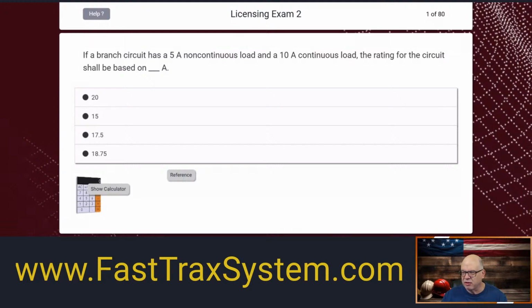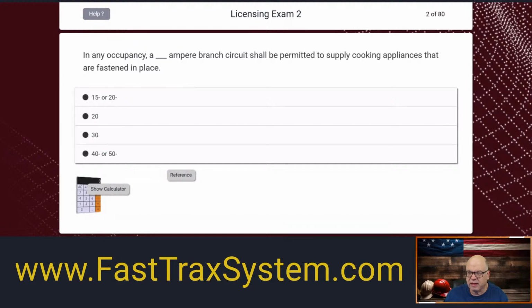All right, so let's do the math here. We have to do the continuous load at 125%, and that was 10. So 10 times 1.25 is 12.5, if y'all can see that. So 10 at 125% would be 12.5. And then remember, it said the sum of the value of the non-continuous load, which is 5. So 12.5 plus 5 equals 17.5. 17.5 is this one here. We'll click it, and it doesn't give us the answer, but I am going to tell you what the answer is.